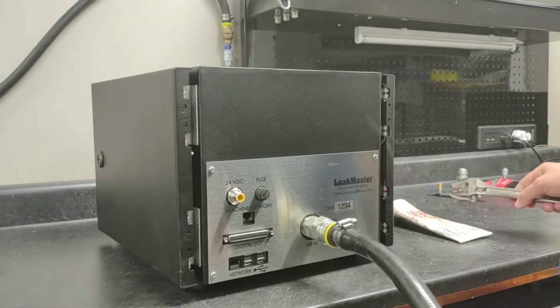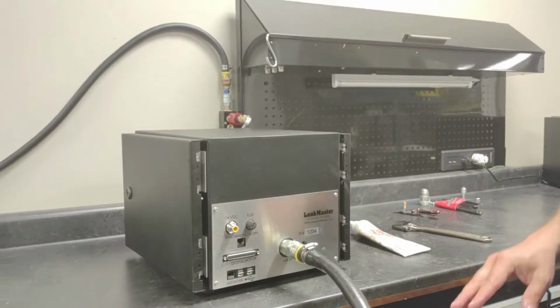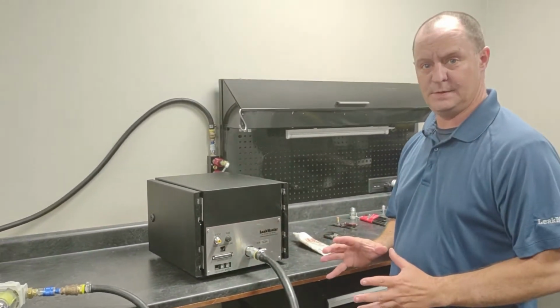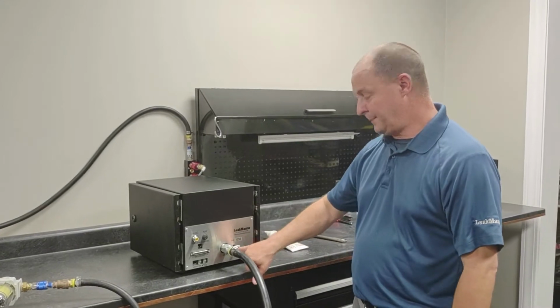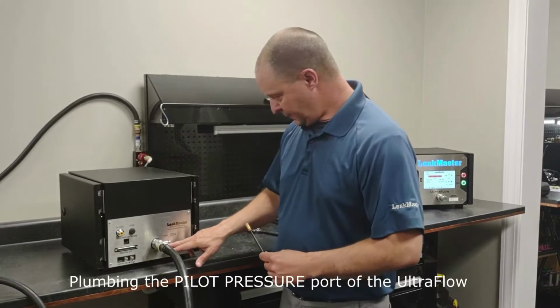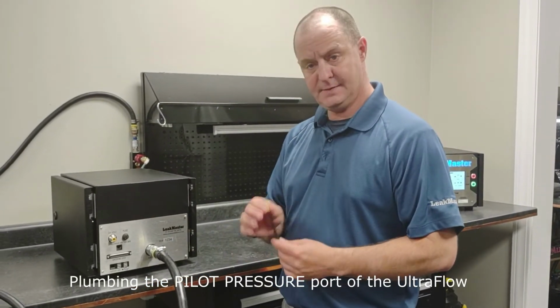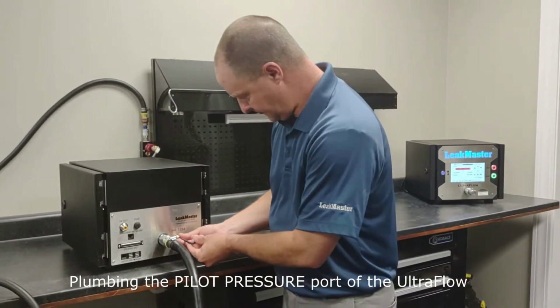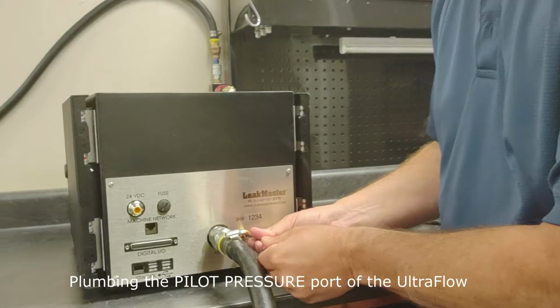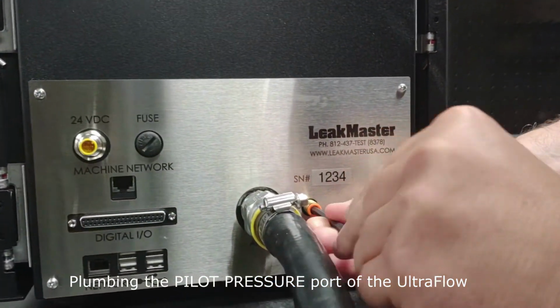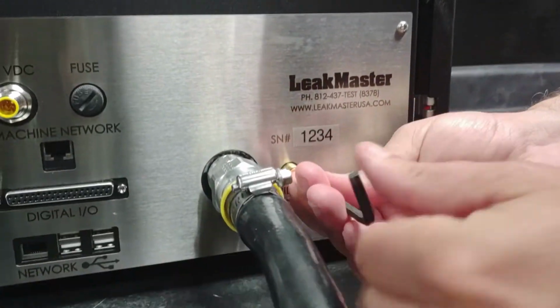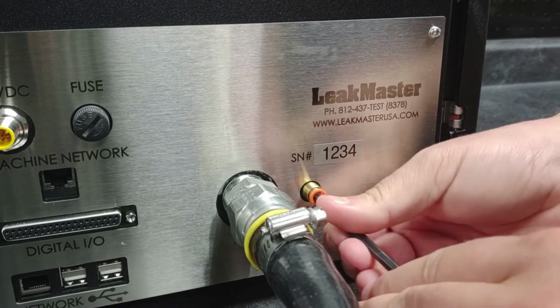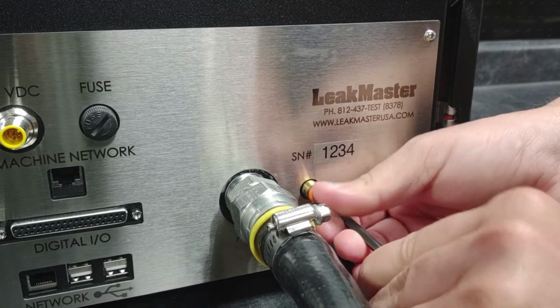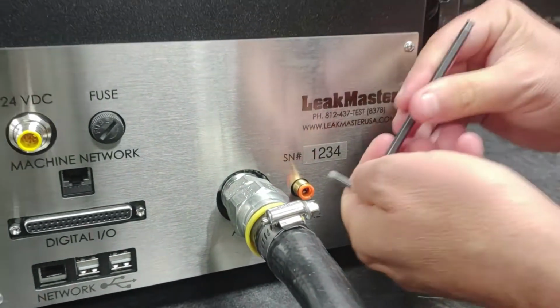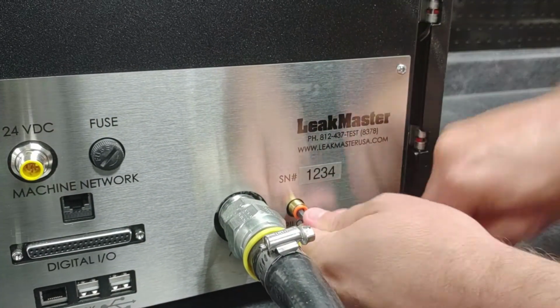Snug it up. So now we've got air plumbed into the unit. Next step is going to be supplying pilot pressure to the instrument. The pilot pressure port is 1/8 inch MPT, so you're going to supply your own fitting of whatever tube or hose size you prefer. For this example, I've got 1/4 inch tubing going into the pilot port, so I'm going to tighten this fitting in real quick.